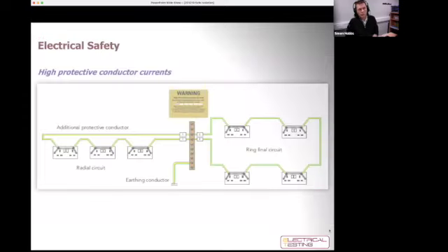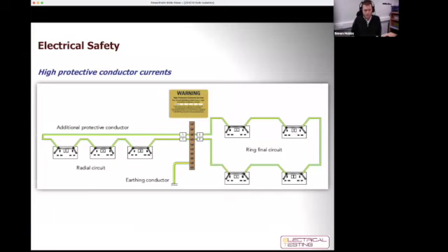Okay, so I preempted myself there because I do have one more thing that I'd like to talk about, which is something that doesn't often get thought about, a bit of an afterthought, which is high protective conductor currents. It's becoming more and more of an issue as we introduce more and more electronic equipment into our installations. As part of their normal operation, many electronic items such as computers, printers, games consoles and so on will cause current to flow in the protective conductor. As we see on the diagram there, the green and yellow is the protective conductor. This is often referred to as earth leakage current.